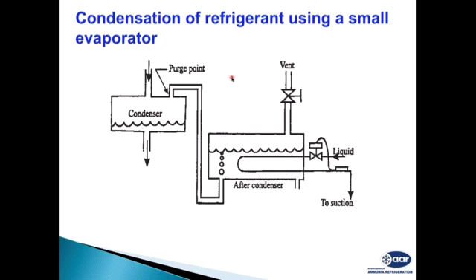The next type uses a refrigerant evaporator, using the refrigerant system which is available with us. In this unit, we have a heat exchanger which is fed liquid from the refrigerant plant itself, and we take the purge points from the condenser or the receiver. They are brought into contact with this heat exchanger. If it is ammonia, it will become liquid and is drained out and put back into the system. If it is non-condensable gases like air, it will be vented out. Normally it is provided with an automatic control system, which senses the difference between ammonia and non-condensable gases, and it will vent out when the vessel is full of non-condensable gases.